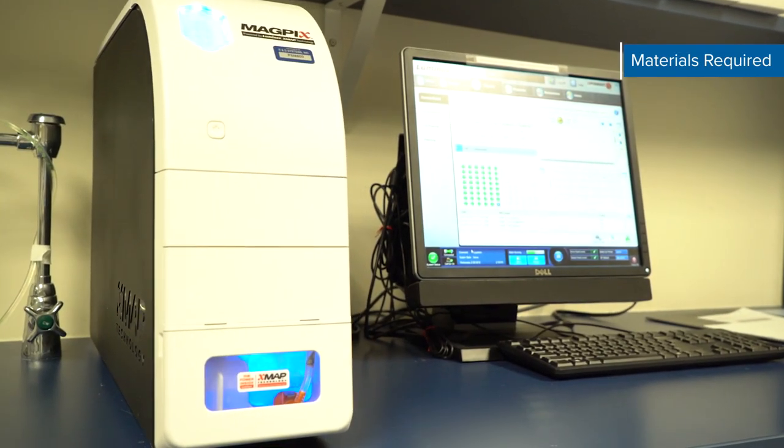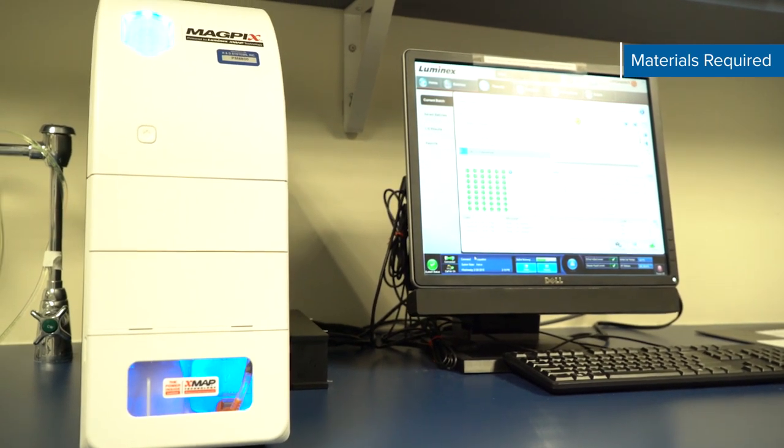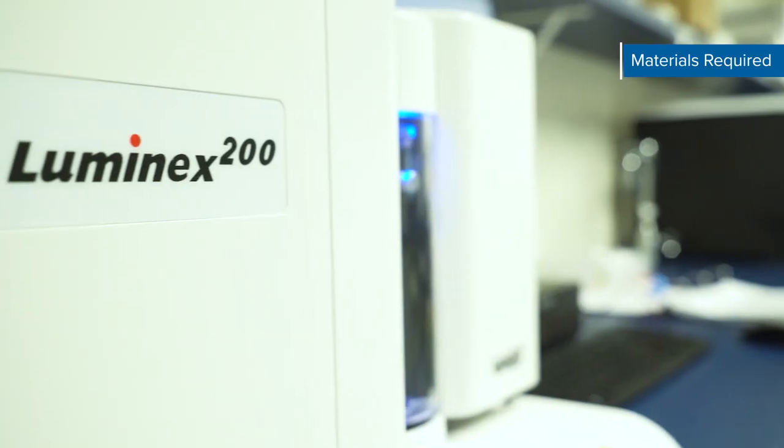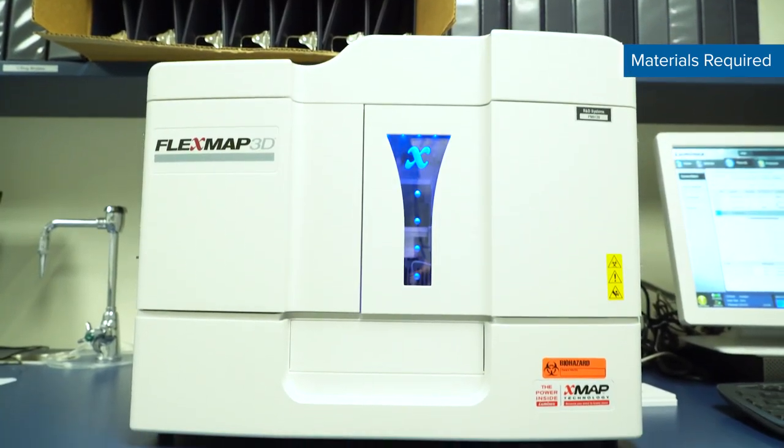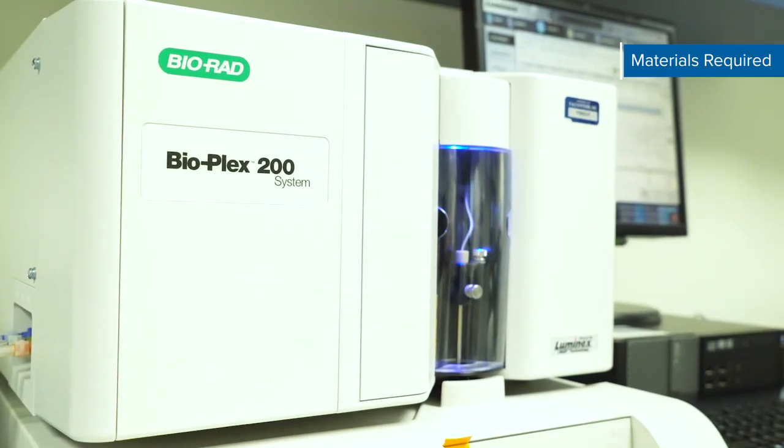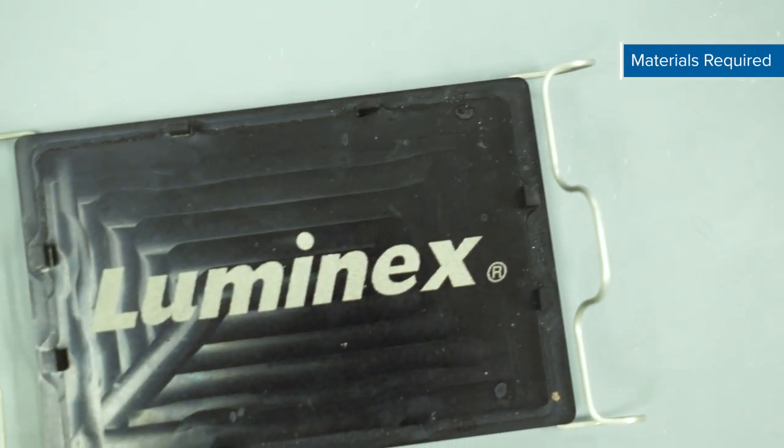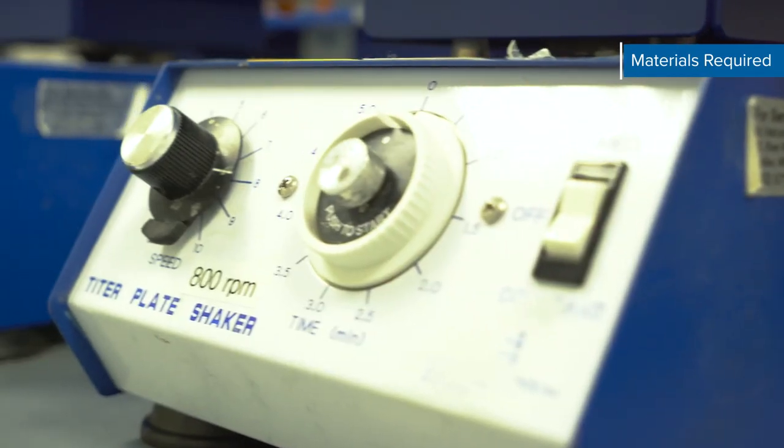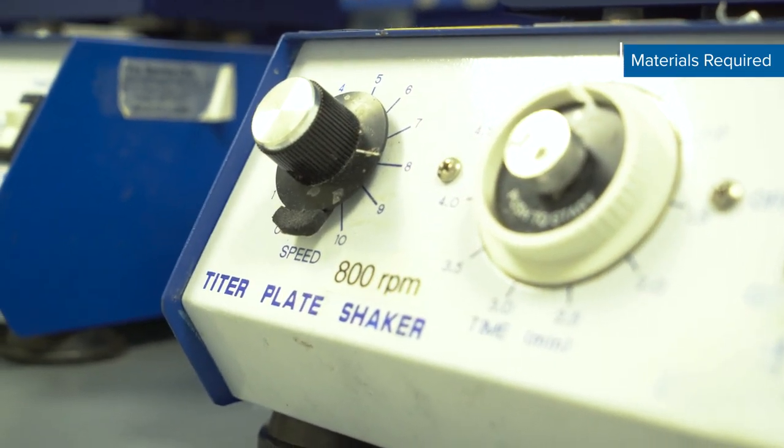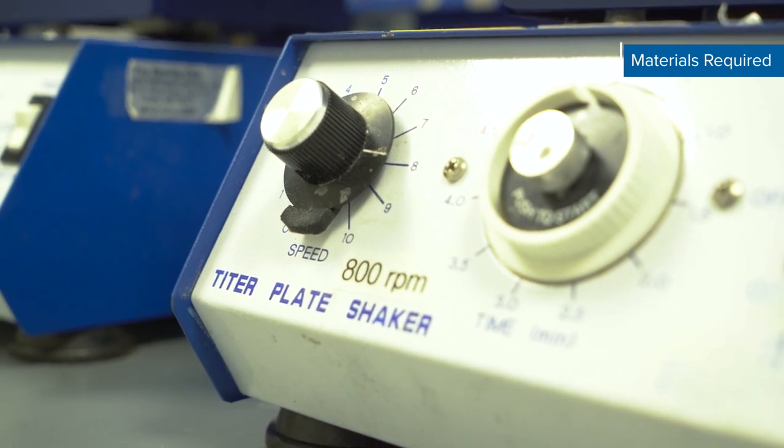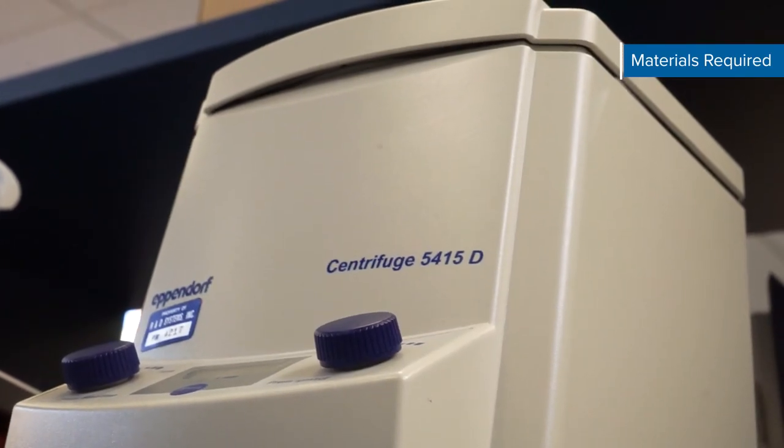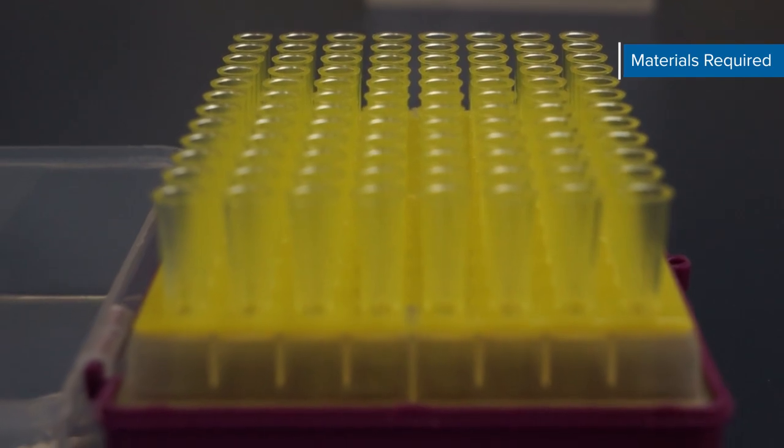In addition to the kit contents, you'll also need a compatible instrument like a MagPix, Luminex 100-200, FlexMap 3D, or BioRad BioPlex, a handheld microplate magnet or plate washer with a magnetic platform, a horizontal orbital microplate shaker capable of maintaining a speed of 800 plus or minus 50 RPM, a microcentrifuge, and general lab supplies.